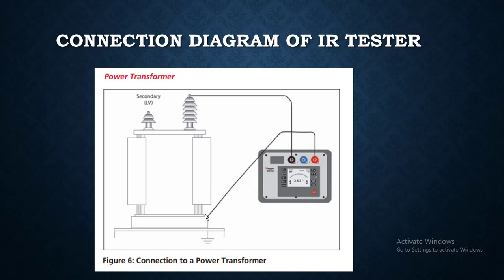If you wish to test with the LV bushing, you can change this lead from ground to LV and check the insulation between HV to LV. Another option is the current connection showing insulation testing between HV to ground.